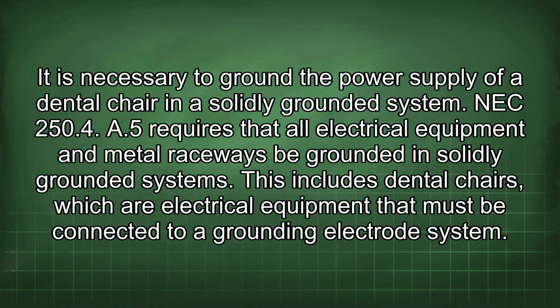It is necessary to ground the power supply of a dental chair in a solidly grounded system. NEC 250.4(A)(5) requires that all electrical equipment and metal raceways be grounded in solidly grounded systems. This includes dental chairs, which are electrical equipment that must be connected to a grounding electrode system.